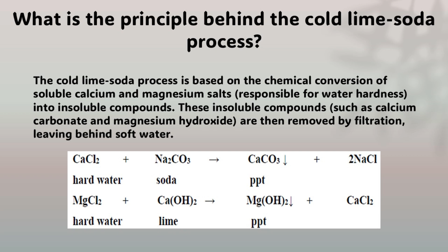The next question is: question number 31. What is the principle behind the cold lime soda process? The answer to this question is: the cold lime soda process is based on the chemical conversion of soluble calcium and magnesium salts, responsible for water hardness, into insoluble compounds. These insoluble compounds, such as calcium carbonate and magnesium hydroxide, are then removed by filtration, leaving behind soft water.